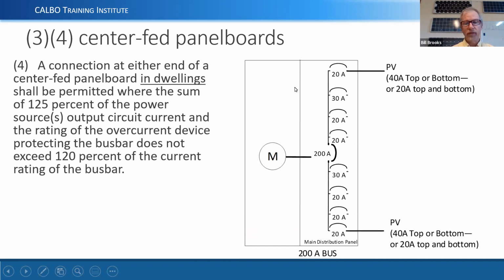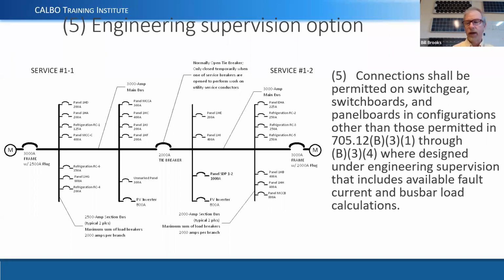Center-fed panels. A lot of people like to talk about center-fed panels. Code allows specifically that we can use the 120% rule on dwellings with center-fed panels. So on a 200 amp center-fed panel like this, we could put a 20 amp breaker on either end, or we could put a 20 amp breaker on both ends, or a 40 amp breaker on either end, not both ends. That is totally allowed, and that was getting away from the problem that had occurred where a lot of jurisdictions were requiring people to change out perfectly good center-fed panel devices. Okay, and it was because of an article they read that was not really accurate.